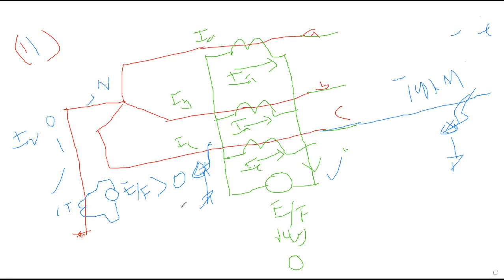So this is the problem for us, right? That's why this is called unrestricted earth fault protection. It doesn't have any limitation or boundary of the area, such that within this region, if an earth fault occurs, this relay will operate. This provision is not integrated here. Understood?